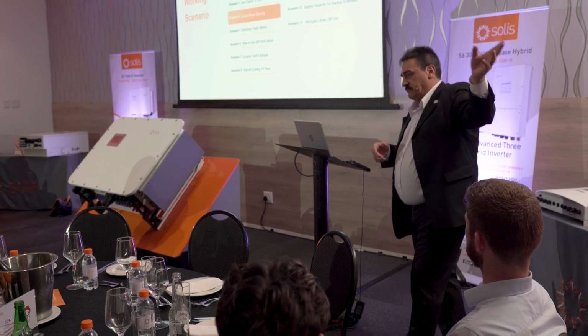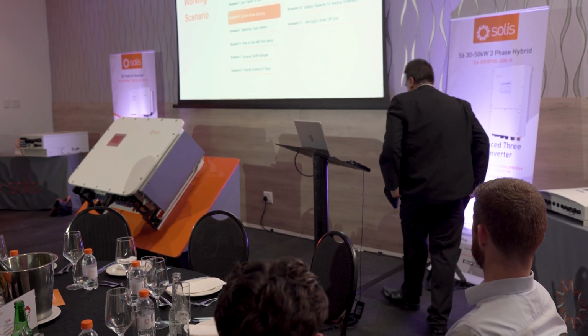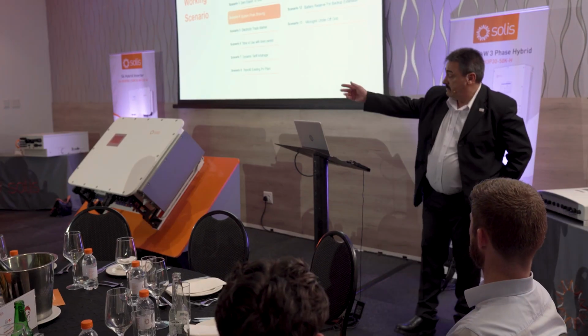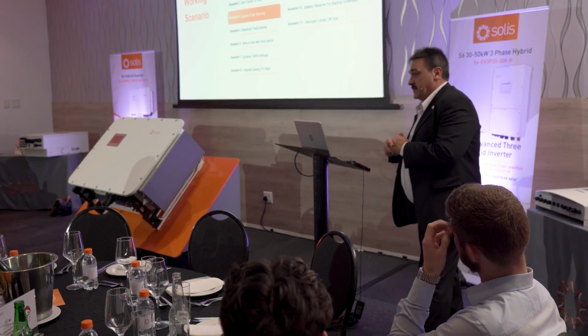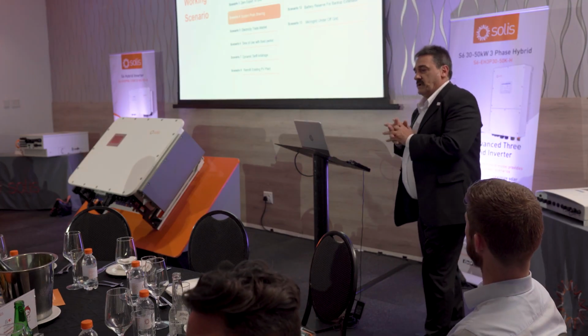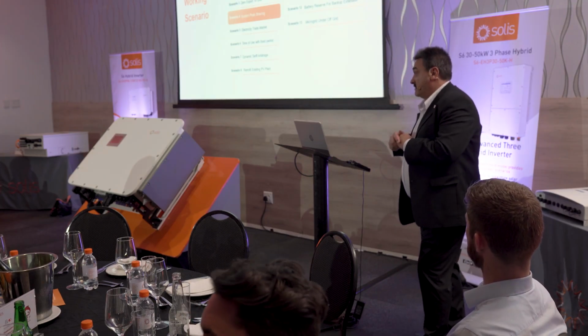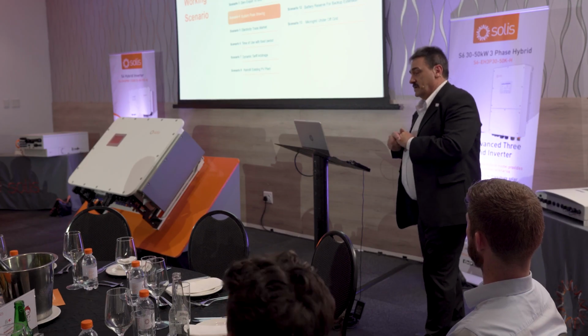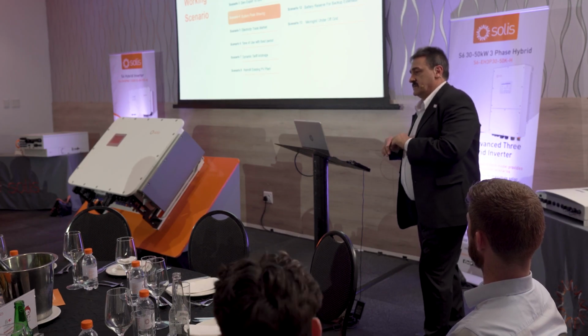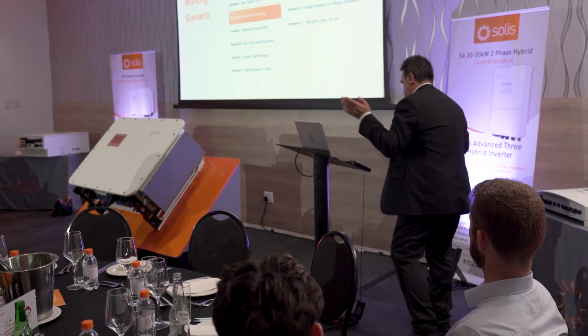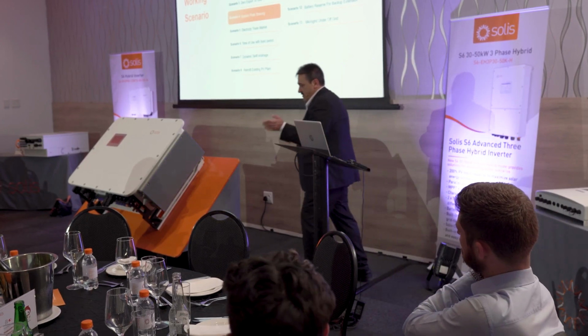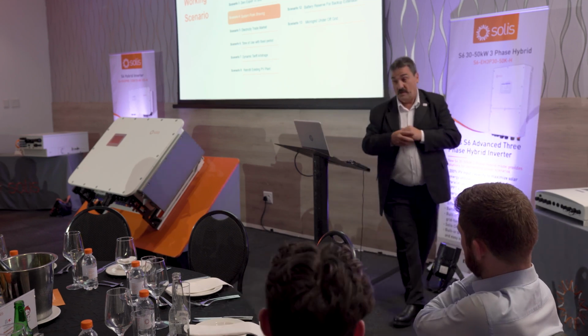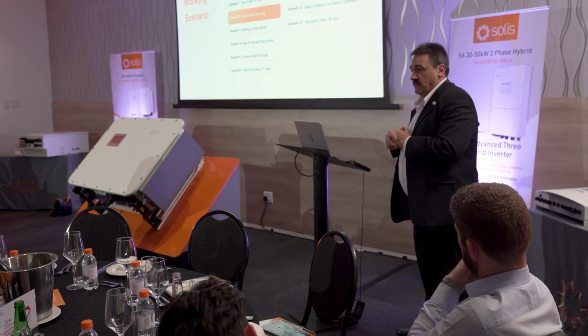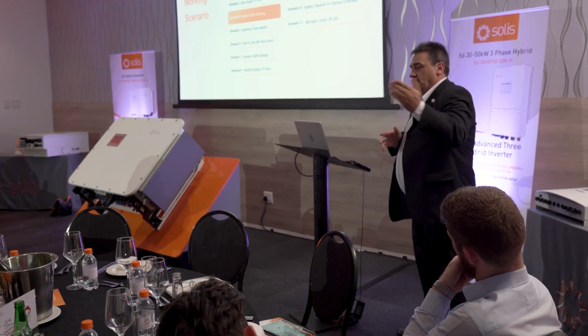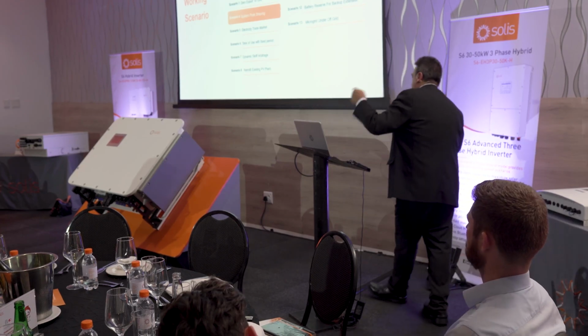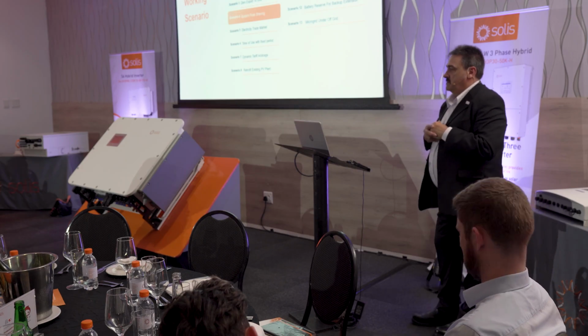We actually have a pretty good peak shaving example running at a hotel in Port Elizabeth. There's 350 kilowatts in there, not quite this one, but the operation is the same. The whole place runs through it, controlled at 75 kilowatts input from the grid. It doesn't go over, it's always controlled. In the event of a backup or electricity problem, they don't even know they have a problem because the system just carries on working. It's a perfect example, and it works really well. That hotel, the minute they go over 75 kilowatts, their kilowatt hour price doubles immediately.